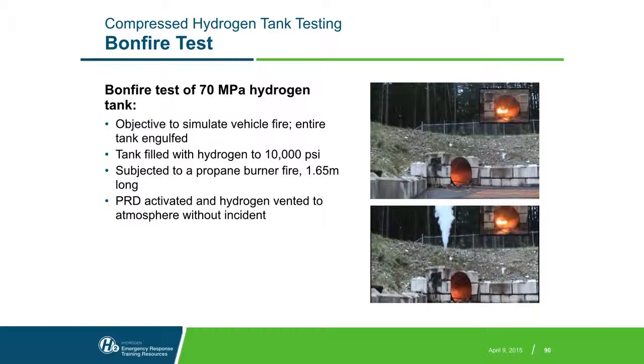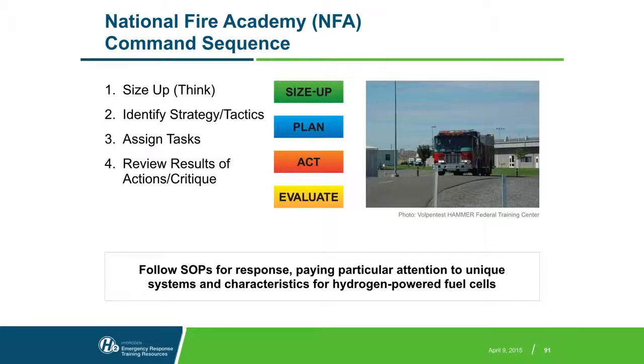The reason for the steam there is actually condensated water. They had a high water content in the hydrogen that day, so it's a side effect. But the point being that it vents the contents of the hydrogen and doesn't rupture as a result of the fire. So in terms of what to do in a response, we are not here to give you tactics. The goal here is to give you information that, as first responders, you can add into your standard operating procedures for responding. In this slide session, we have adopted the National Fire Academy command sequence, and I'm only going to highlight a few items from this sequence.